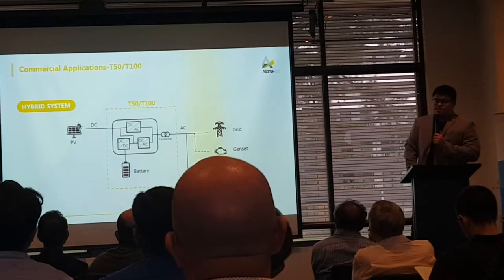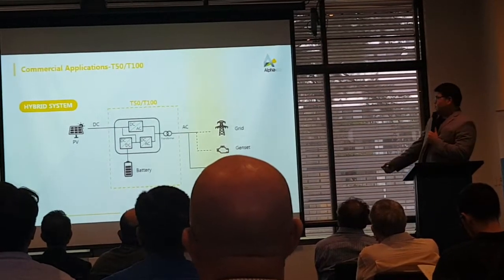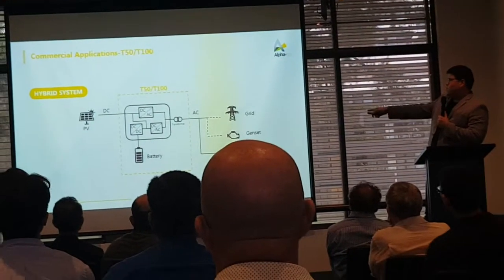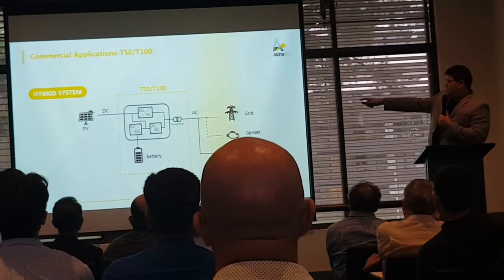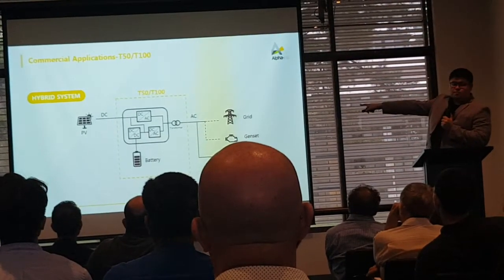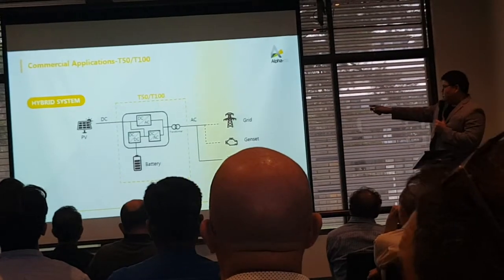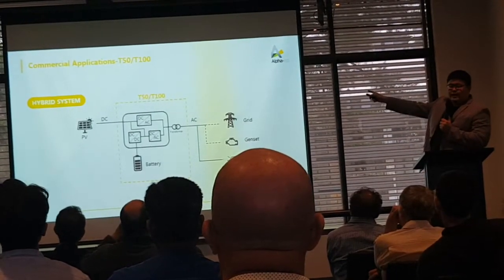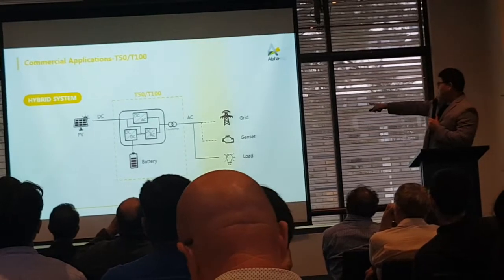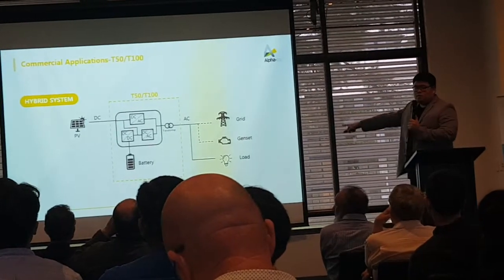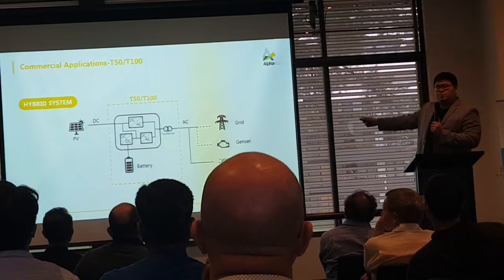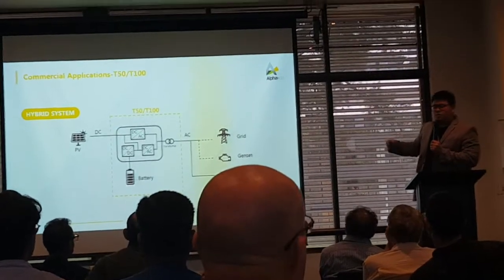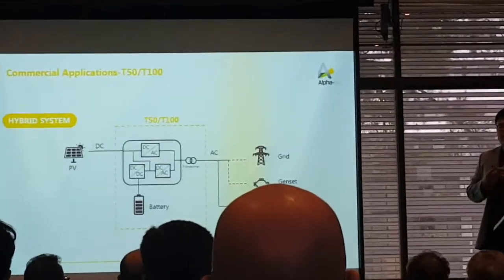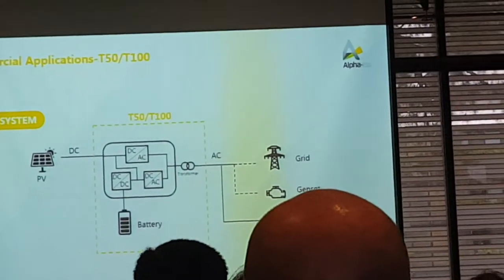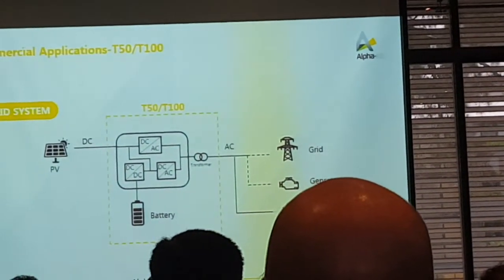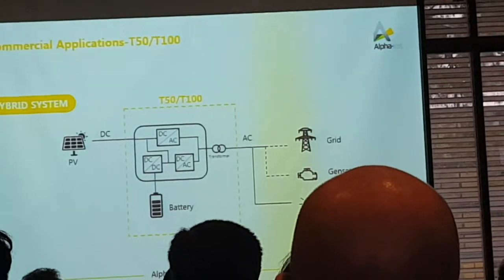So for the T50, T100, you have the hybrid system. This is normally how you connect it: PV connected directly into the system with one MPPT, and then another PV system AC coupled into the system as well. Then you have grid, generator, and load on the AC side. This can also be the backup. In off-grid application, they can also put out 100 kilowatts on 3 phases, so 33.33 kilowatts per phase.